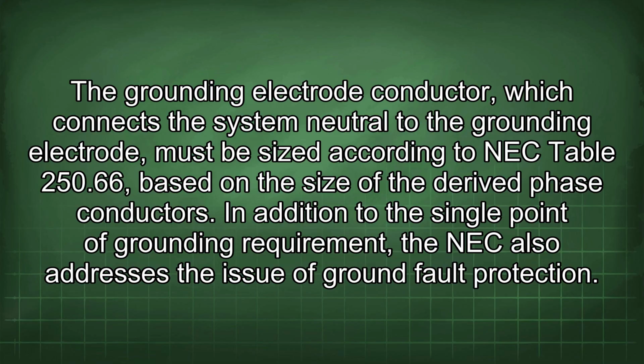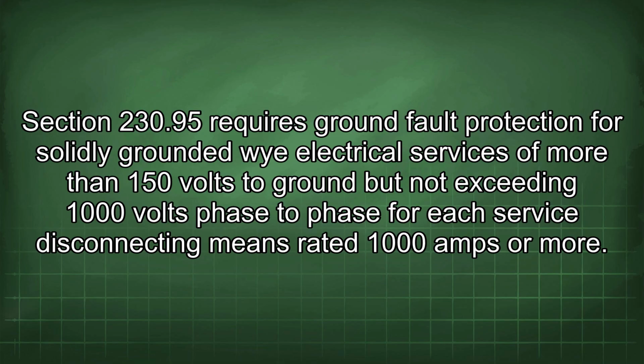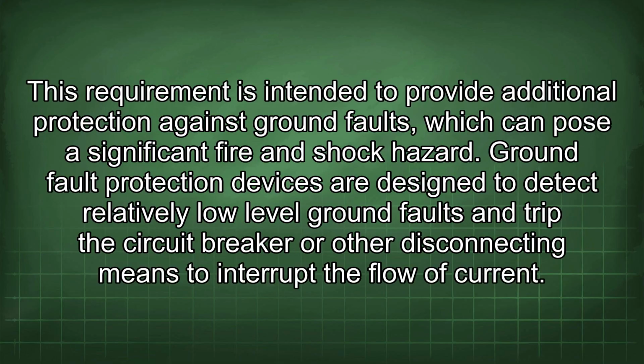In addition to the single point of grounding requirement, the NEC also addresses the issue of ground fault protection. Section 230.95 requires ground fault protection for solidly grounded wye electrical services of more than 150 volts to ground but not exceeding 1000 volts phase to phase for each service disconnecting means rated 1000 amps or more. This requirement is intended to provide additional protection against ground faults, which can pose a significant fire and shock hazard. Ground fault protection devices are designed to detect relatively low-level ground faults and trip the circuit breaker or other disconnecting means to interrupt the flow of current.